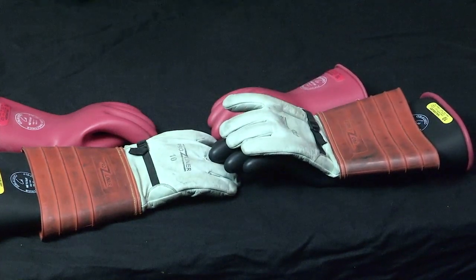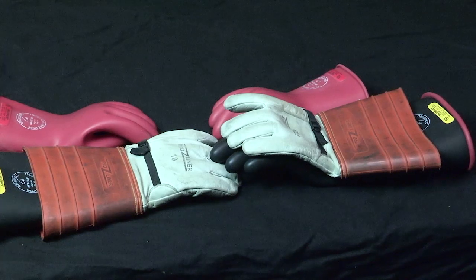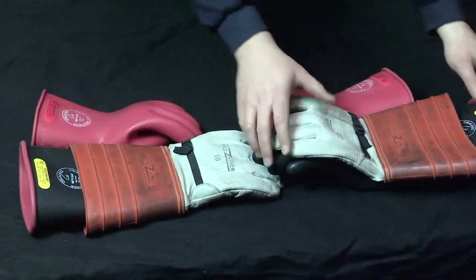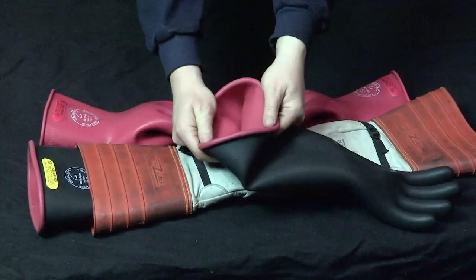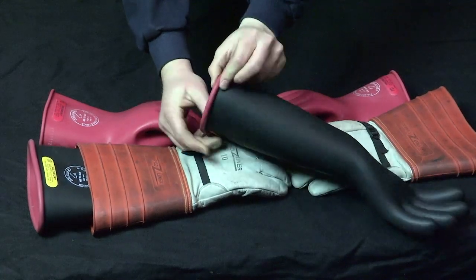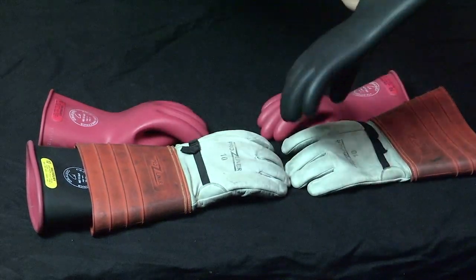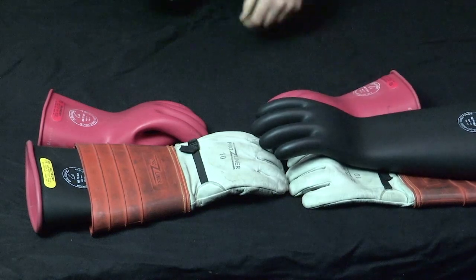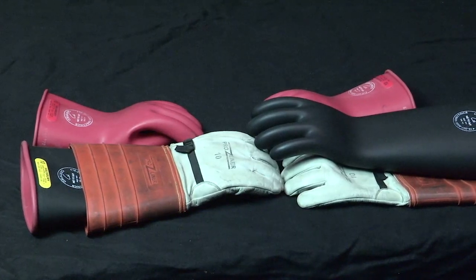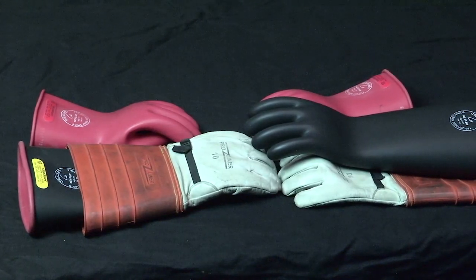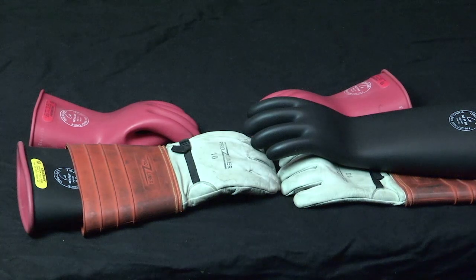Minor cuts and abrasions to the outer black surface of the glove are permitted if the contrasting inner color does not show through. The inner yellow or red part of the glove represents 80% of the glove thickness. It is not possible to determine in the field just how deep a cut or abrasion may be. Therefore, any break on the inside of the rubber glove renders the glove defective. It must be returned to the work location for replacement.